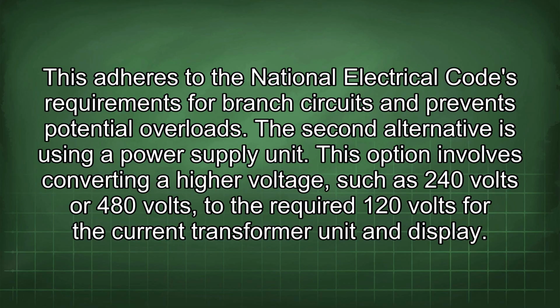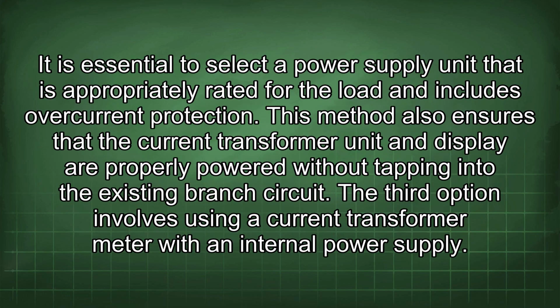The second alternative is using a power supply unit. This option involves converting a higher voltage, such as 240 volts or 480 volts, to the required 120 volts for the current transformer unit and display. It is essential to select a power supply unit that is appropriately rated for the load and includes overcurrent protection. This method also ensures that the current transformer unit and display are properly powered without tapping into the existing branch circuit.